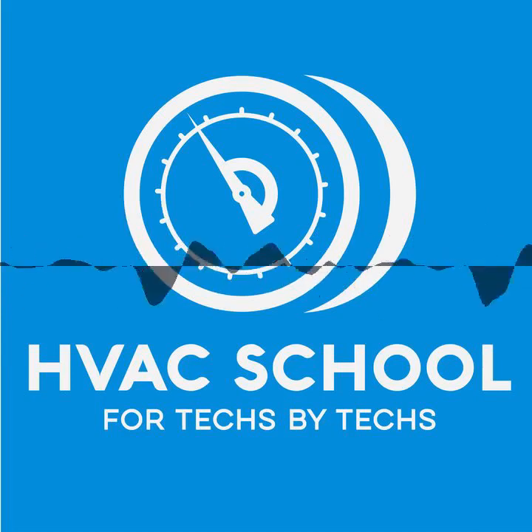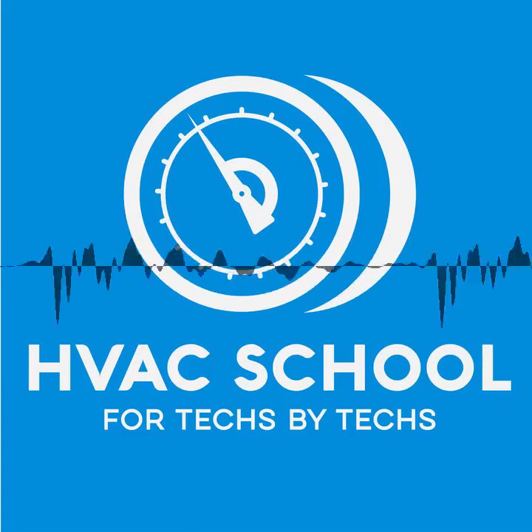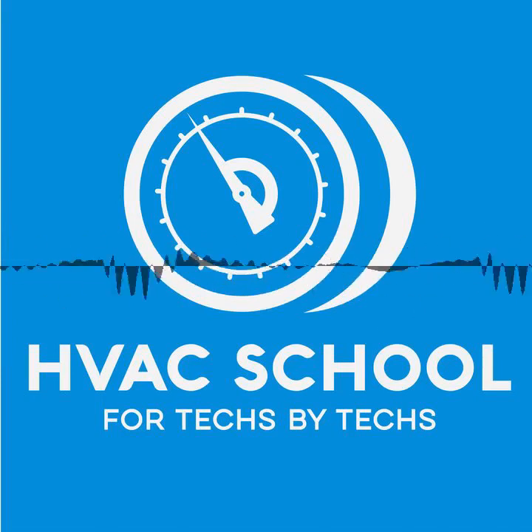So for guys who are used to working in residential or commercial, you may hear "motor starter" and think, because I did for several years before I started working on larger equipment, that it was like a start capacitor for a 3-phase motor or something. It's actually a big contactor usually, and it's got an overload in it. Like Eric said, in a lot of cases, when you have a starter, the motor itself may not be internally overload protected. Do you see that on these pumps?